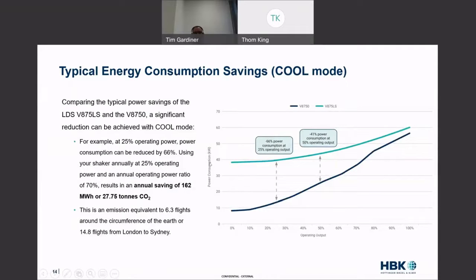So here on this slide, on the right-hand side, we have another graphic which is showing us the difference in power consumption of the V8750 versus the V875LS. If we look at comparing the typical power savings of these two machines, you can see that there is a significant reduction when operating the V8750 with cool mode. So, for example, at 25% operating power, consumption can be reduced by 2/3. Using the shaker annually at 25% operating power and an annual operating power ratio of 70%, this results in an annual saving of 162 megawatt hours, or nearly 28 tons of CO2.